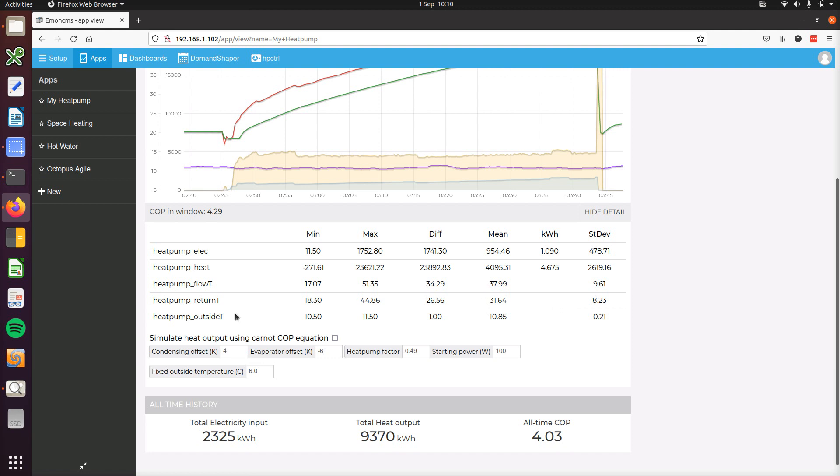Finally at the bottom here there's a new tool that can be quite useful if you haven't got heat metering. It uses the Carnot COP equation for the heat pump to simulate the heat output. It uses the flow temperature and the outside temperature to calculate that COP, then multiplies that COP by the electricity consumption to estimate the heat output.